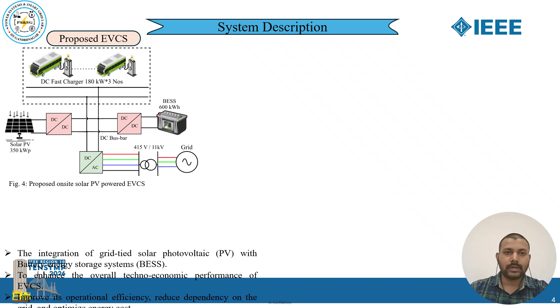This figure illustrates the proposed grid-interactive EV charging station architecture. The system consists of three 180 kilowatt DC fast chargers, a 350 kilowatt solar PV plant, and a 600 kilowatt battery energy storage system, connected to the utility grid through an 11 kV / 415 V transformer into the existing network. All energy resources are integrated through a common DC bus, which enables flexible power sharing among the PV system, battery, EV chargers, and grid.